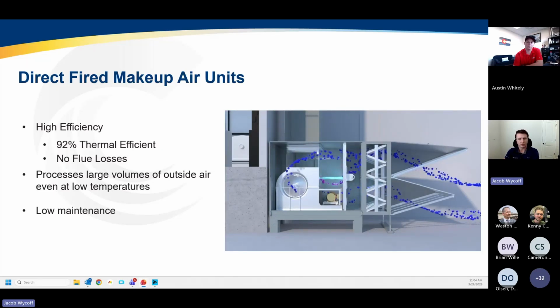They're also extremely simple, low maintenance, reliable pieces of equipment that's able to last for a very long time. Typical lifespan anywhere from 20 to 30 years on these units. These manufacturing facilities, they really want to focus on manufacturing the goods they went in business to do. They don't want to worry about their unit firing up. They just want to know that on the coldest day of the year, when they need that heat, when they need that ventilation, their unit outside is going to provide that.